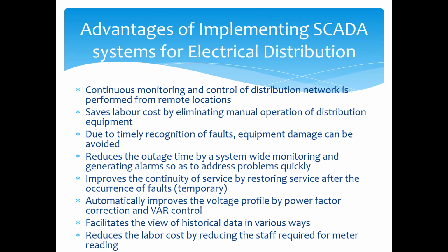Traveling from place to place takes a lot of time, so we can avoid that by doing control through a SCADA network. Due to timely recognition of faults, equipment damage can be avoided. If we can timely recognize the fault, we can isolate those sections and avoid equipment damage.